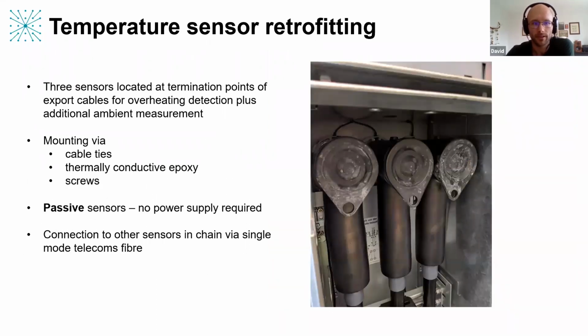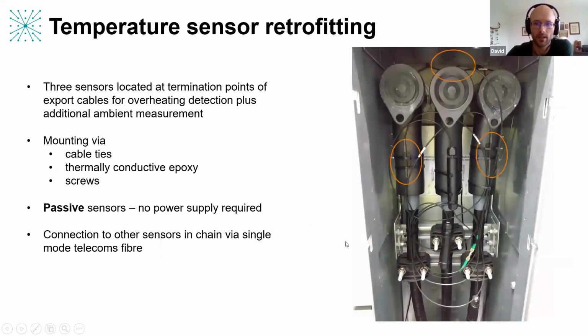Next in the line, we've installed temperature sensors to monitor overheating of the cable terminations you can see here. So we've installed 3 sensors on these cable terminations, and then an additional 4th sensor to measure ambient temperature. These sensors can be retrofitted quite easily, either using cable ties, thermally conductive epoxy, or screws, depending on the sensor type or the surface you want to mount to. And again, these temperature sensors are passive, so no power is required here. All we require is connection to the interrogator or other sensors in the line via optical telecoms fiber, which makes the whole installation process straightforward and quite easy.